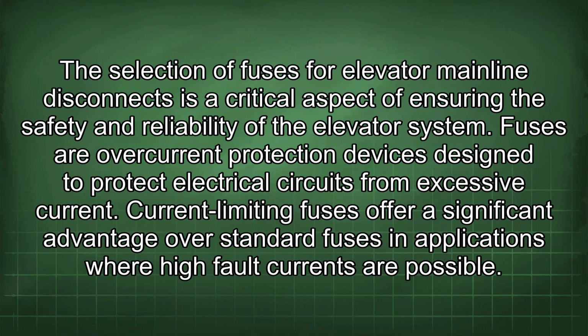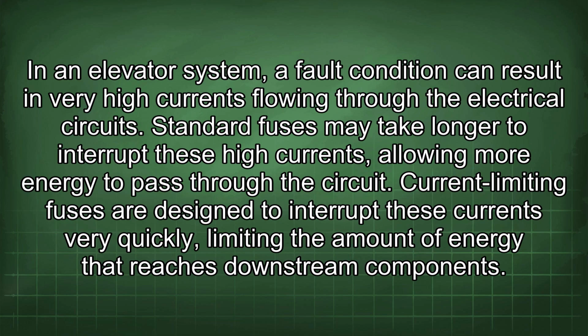The selection of fuses for elevator mainline disconnects is a critical aspect of ensuring the safety and reliability of the elevator system. Fuses are overcurrent protection devices designed to protect electrical circuits from excessive current. Current-limiting fuses offer a significant advantage over standard fuses in applications where high fault currents are possible. In an elevator system, a fault condition can result in very high currents flowing through the electrical circuits. Standard fuses may take longer to interrupt these high currents, allowing more energy to pass through the circuit. Current-limiting fuses are designed to interrupt these currents very quickly, limiting the amount of energy that reaches downstream components.